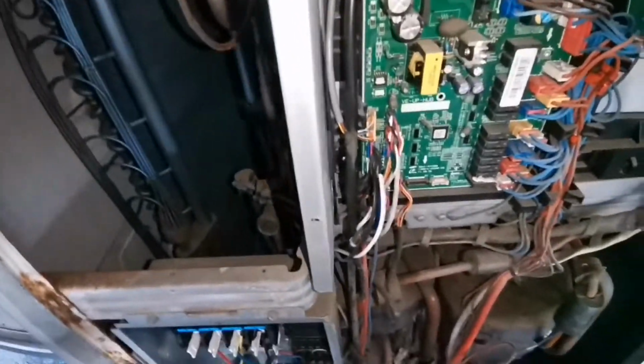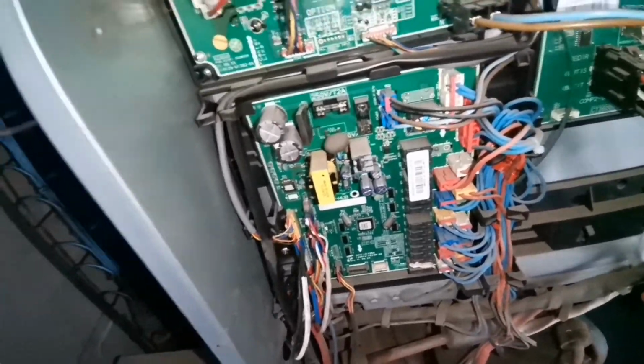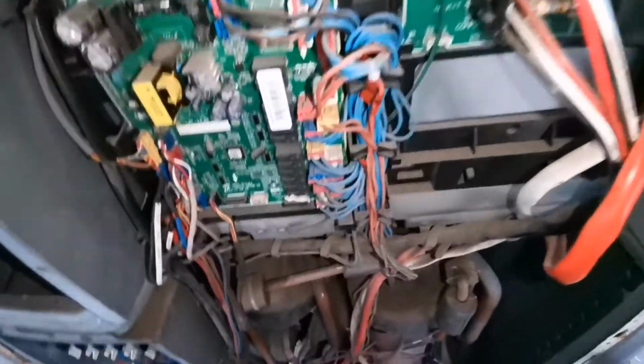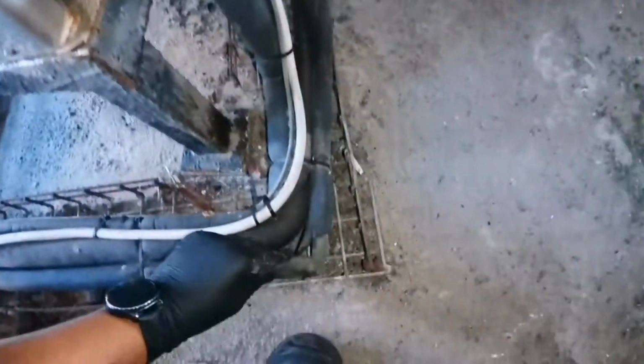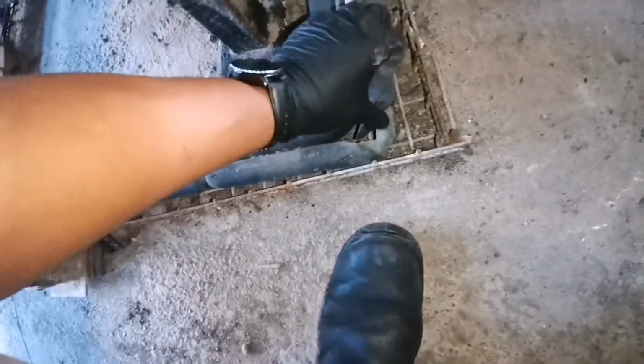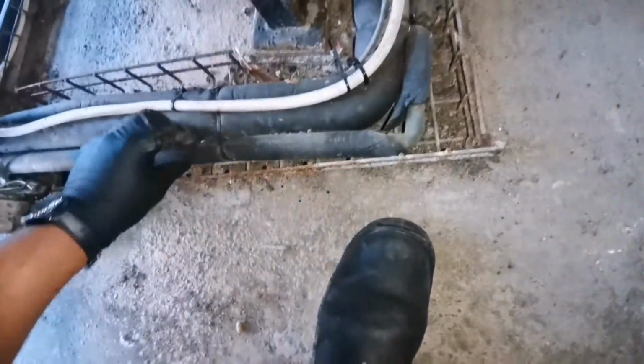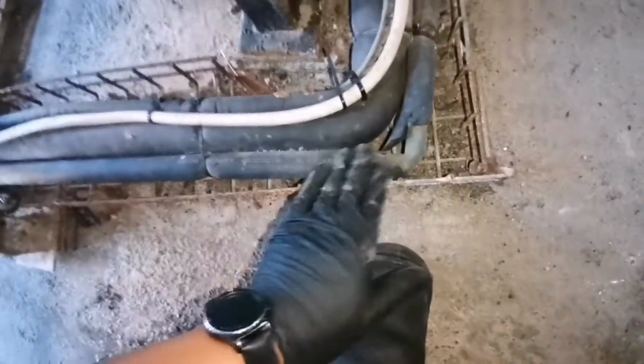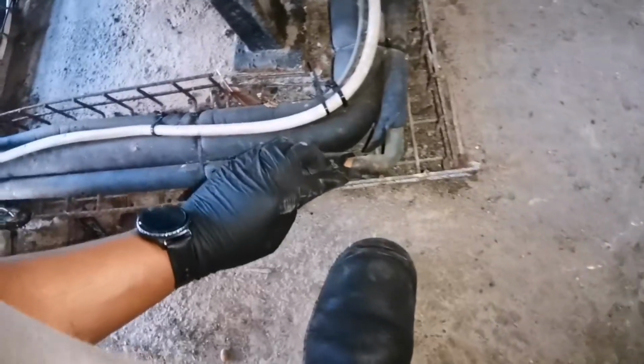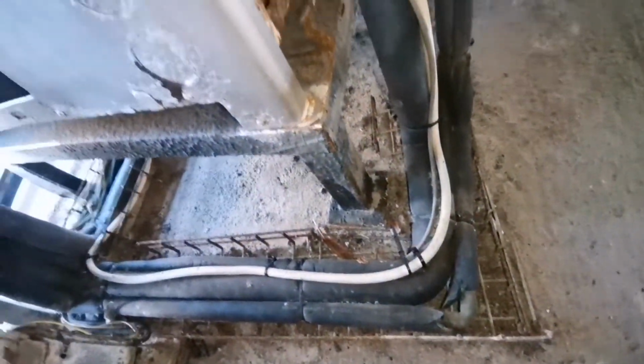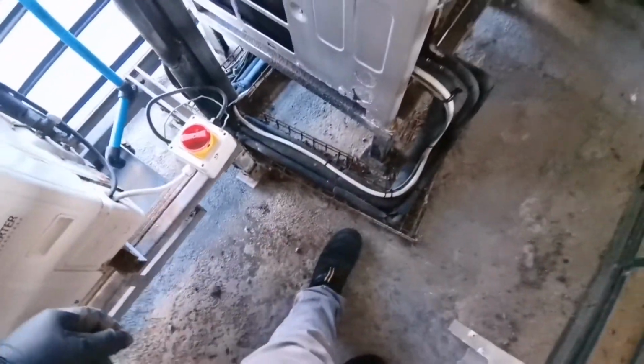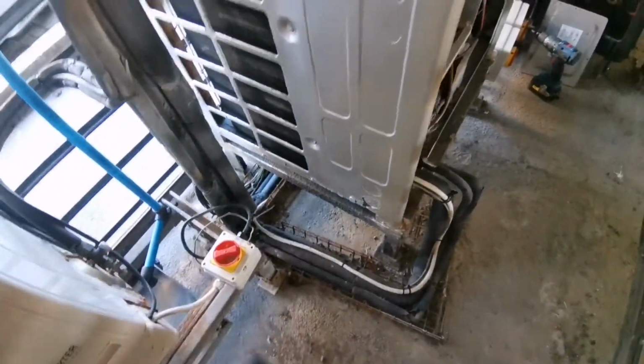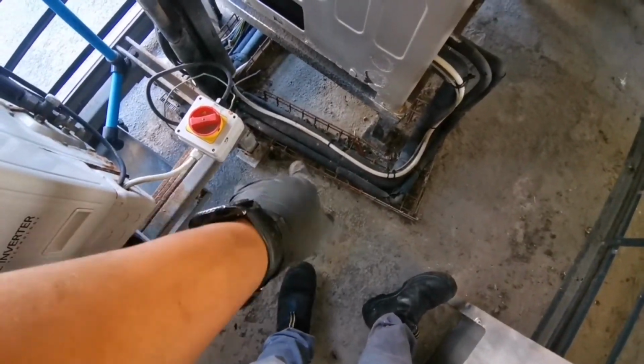So yeah, before we do anything else, that's what we're going to do. Then we'll have to put on a heat pump bidirectional liquid line dryer. Let's have a look, see what's going on here. Okay. So we'll get one. I'll probably get the one that I normally get, which comes in 7/8 sweat on. So we'll put a liquid line dryer over there.